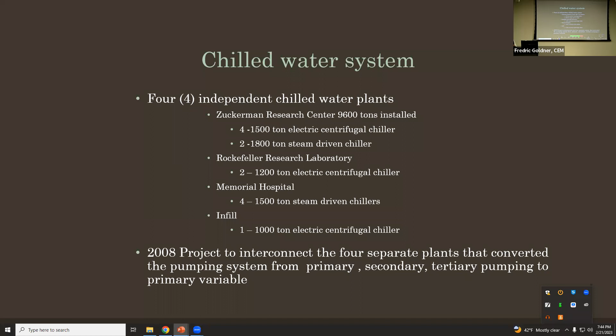So we did the project, interconnected the plants. We eliminated 17 tertiary pumps and 4 primary pumps, lowered the overall demand by a megawatt of power, which the institution used right away for other renovations and ORs. But now we dispatch the chillers from the most efficient to the least efficient. Our load varies from 500 tons in the winter for process loads to our peak load last summer was 11,500. And we're also able to participate in demand response because I have all of these chillers on standby. I can flip over to steam chillers and reduce the overall demand by about 3 megawatts.